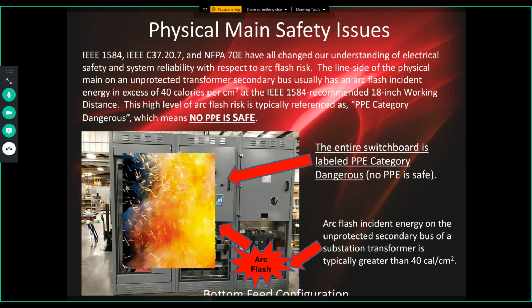When we look at secondary virtual main issues and the disadvantage of physical mains, we can see that the arc flash incident energy on the line side of that breaker is almost always greater than 40 calories per centimeter squared. And I want to be clear, that means this entire switchboard is PPE category dangerous. One of the things that drives me crazy when I see power system studies is that there are people who do power system studies who know how to use the modeling software. They know how to use SKM or EasyPower or ETAP, and they know how to plug data into boxes. But what they don't take into account is the physical construction of the equipment itself.